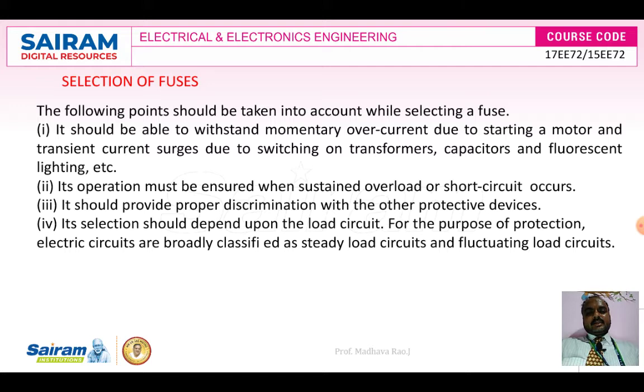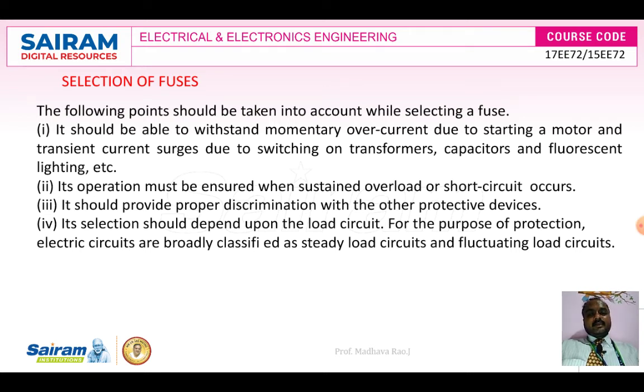Also, to avoid transient current surges, we are selecting the fuses. Transient current surges occur when switching on transformers, capacitors, fluorescent lights, etc. To avoid these transient current surges, we select the current rating of the fuses based on their application.